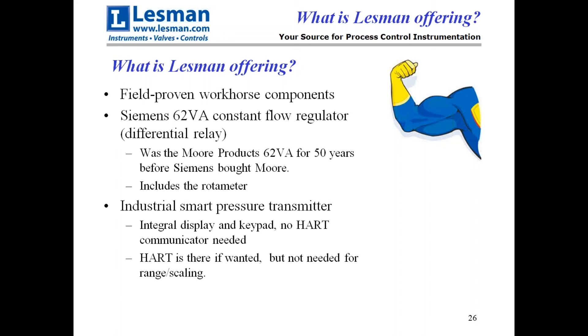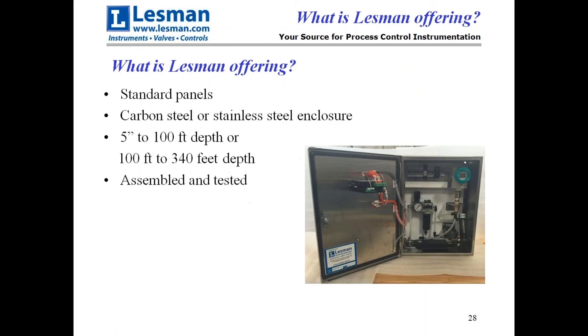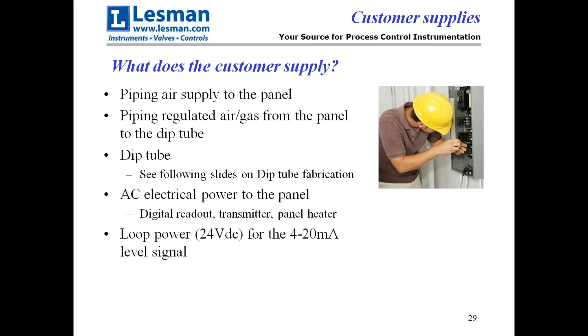The panels come in carbon steel or stainless steel. We have two ranges: 5 inches to 100 feet depth, or 100 feet to 340 feet depth. You need to supply pipe supply air or gas to the panel, pipe the regulated air from the panel out to the dip tube, fabricate a dip tube, and supply AC electrical power to the panel — which powers the digital readout and transmitter. If you want to take the signal back, supply loop power to get the 4-20 milliamp signal out.